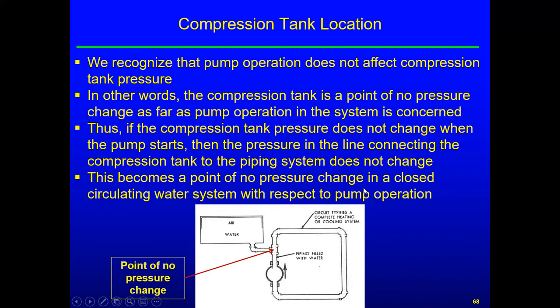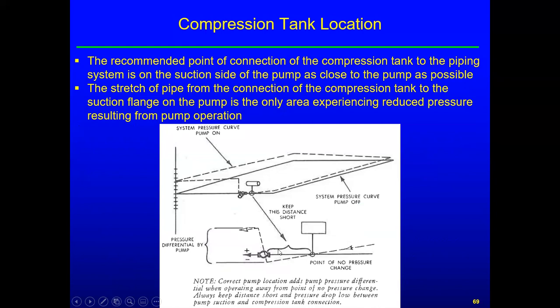So right there, that little red arrow is pointing. You can start the pump or you can turn the pump on and off. You put a pressure gauge, you're not gonna see a change in pressure. Okay. Now, what happens at every other point in the system when you turn the pump on? Every other point in the system does see an increase, or depending on where you put the tank, you could see a decrease in pressure. We'll talk about that in a second.